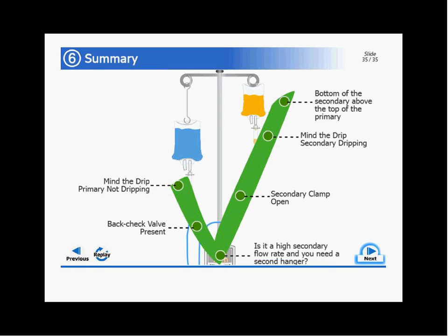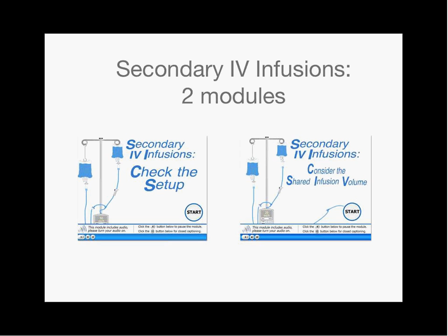The module is called Consider Shared Infusion Volume, and we don't have time today to review the contents of this module, but it really walks through the disagreement between what a pump does and what fluid is actually being administered to the patient, because both the primary and secondary infusions share IV tubing. Use this information to reinforce best practices, such as not connecting a secondary infusion to a high alert primary infusion. It also identifies areas where best practices still need to be established, such as what volume should be programmed in the pump given the shared infusion volume and other factors such as secondary IV bag overfill. So it will stimulate discussions within the hospital, but also with your professional organizations and vendors, because practices still need to be identified and will depend on the pump that you're using.